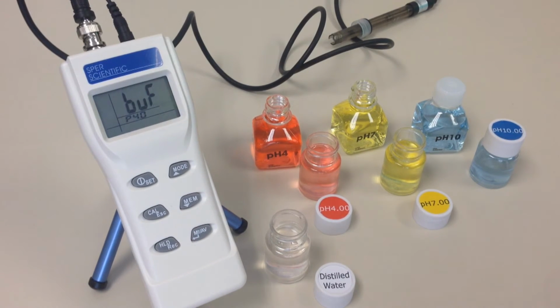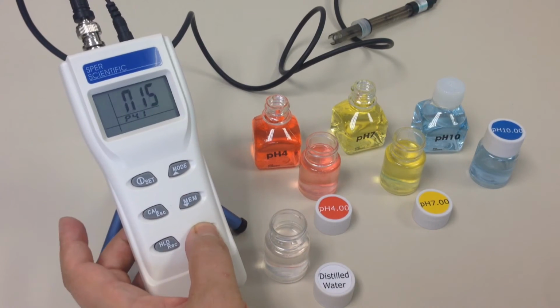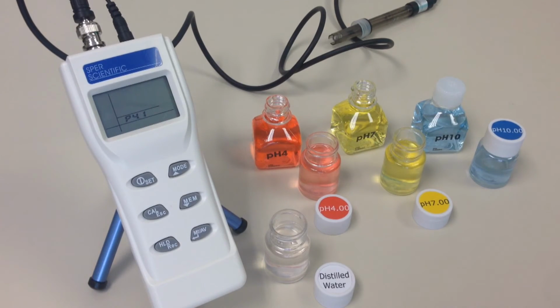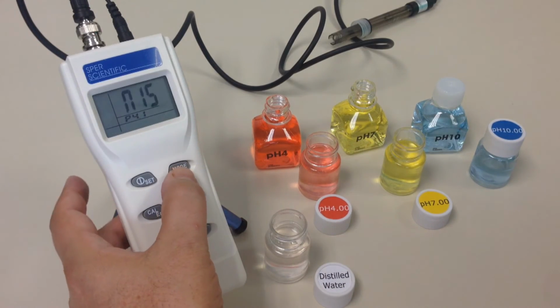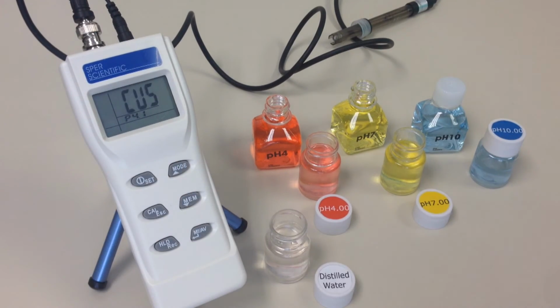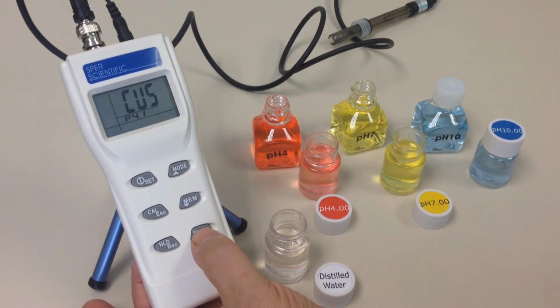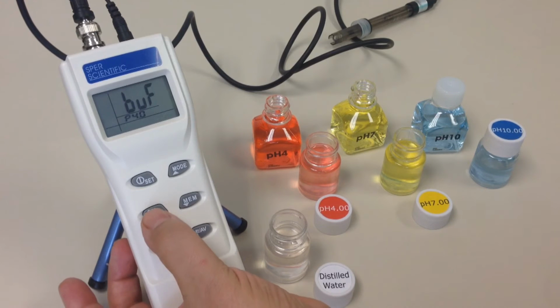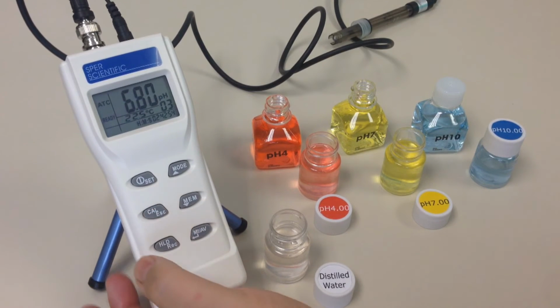So one of the reasons why you may have seen the error 13 message is that you're not calibrating to the right type of solution. So this particular meter comes from the factory ready to go in what's called NIST solution. In this case, since I'm using standard solutions, pH 4, pH 7, or pH 10, I need to change the mode to custom. And it's very simple to do by moving up and have it say CUS. Now to save that mode, you hit the min-max average button again, and you hit the escape button, and we're back to the main screen.